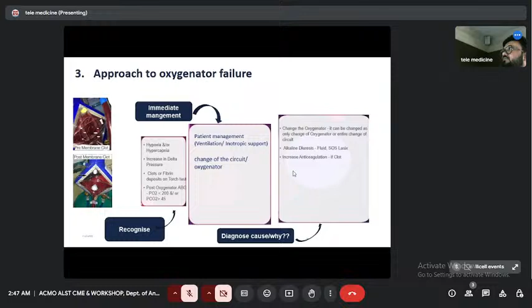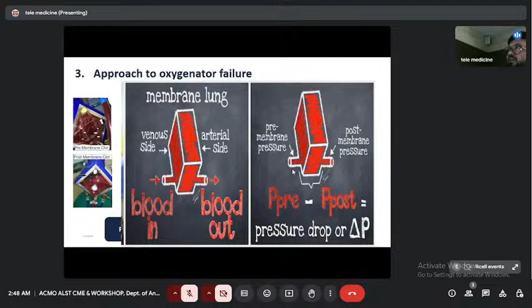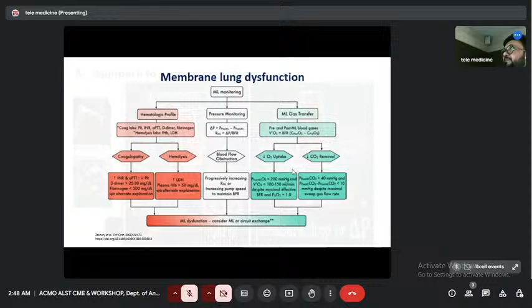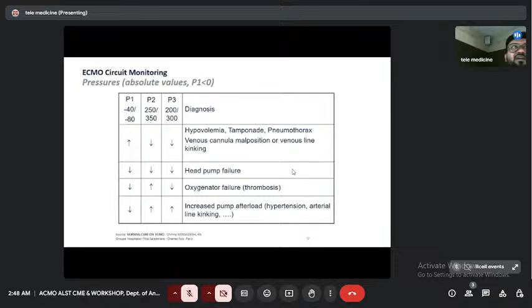So this is one of the clots in the oxygenator. This was discussed previously. This is P1 and P2. If the pressure drop across this, the delta pressure, keeps increasing, that means oxygenator failure. So this is how to approach the lung function. And see the pressures P1, P2, P3, and we have to diagnose accordingly and treat. So this is one of the accidental decannulations. How to manage? Again: clamp, compress, call for help.